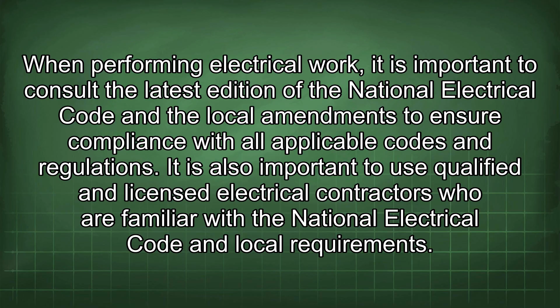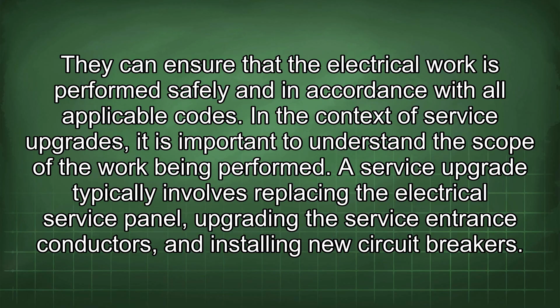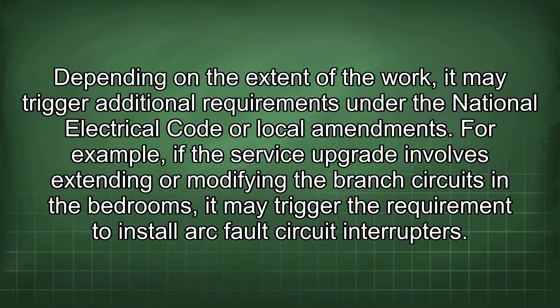In the context of service upgrades, it is important to understand the scope of the work being performed. A service upgrade typically involves replacing the electrical service panel, upgrading the service entrance conductors, and installing new circuit breakers. Depending on the extent of the work, it may trigger additional requirements under the NEC or local amendments. For example, if the service upgrade involves extending or modifying the branch circuits in the bedrooms, it may trigger the requirement to install arc fault circuit interrupters. The authority having jurisdiction can clarify the specific requirements that apply to the project.